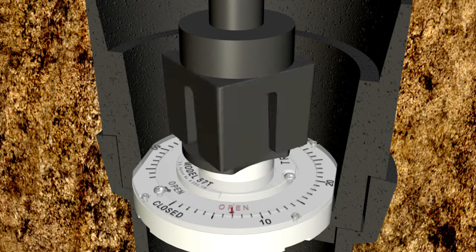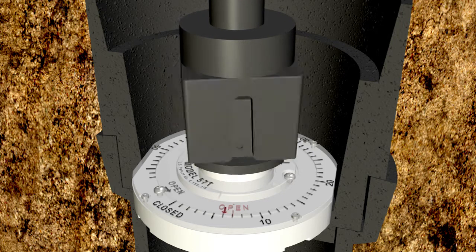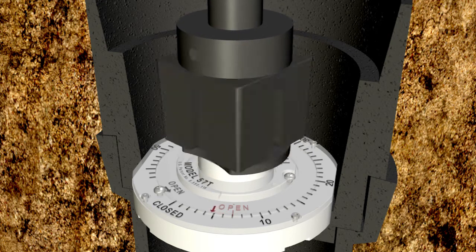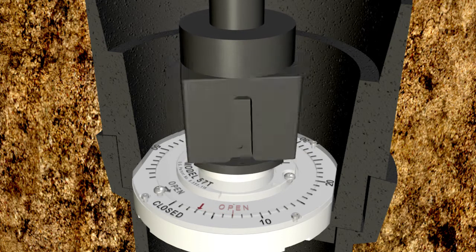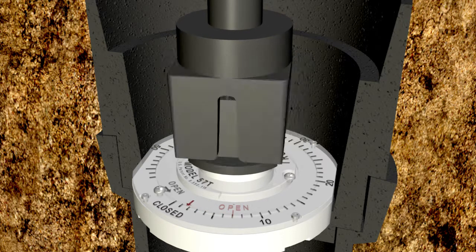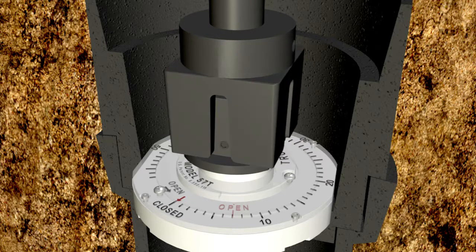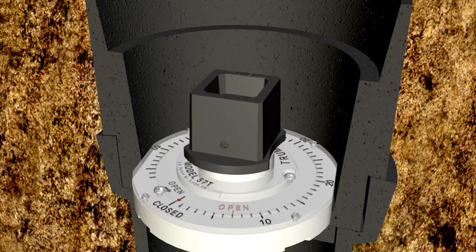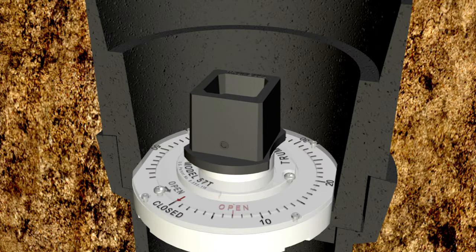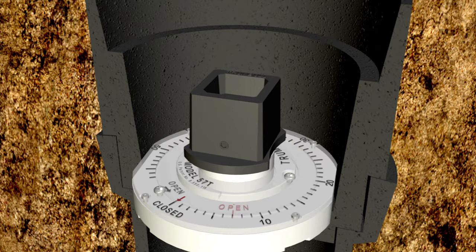Now fully close the valve. The red indicator arrow should now align with the closed mark on the indicator. If it does, you have correctly calibrated your valve and valve position indicator assembly.